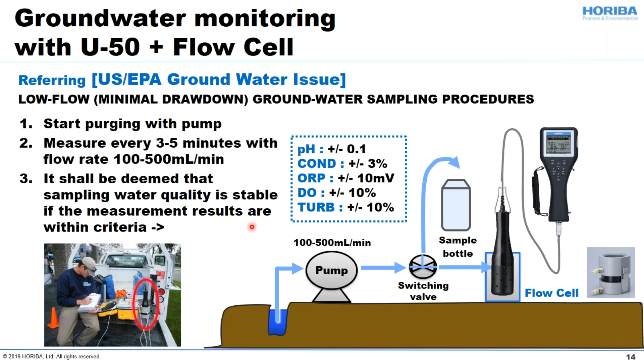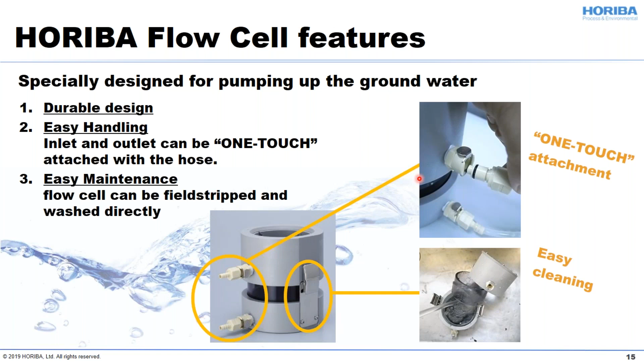This is the detail of the flow cell unit. It has a durable design, the same as the U-50 series, and the maintenance handling is so easy. You can set the sampling hose with just a one-click action, and this flow cell can hold the probe by just one clip, so you can easily strip it and easily wash it directly in the field.